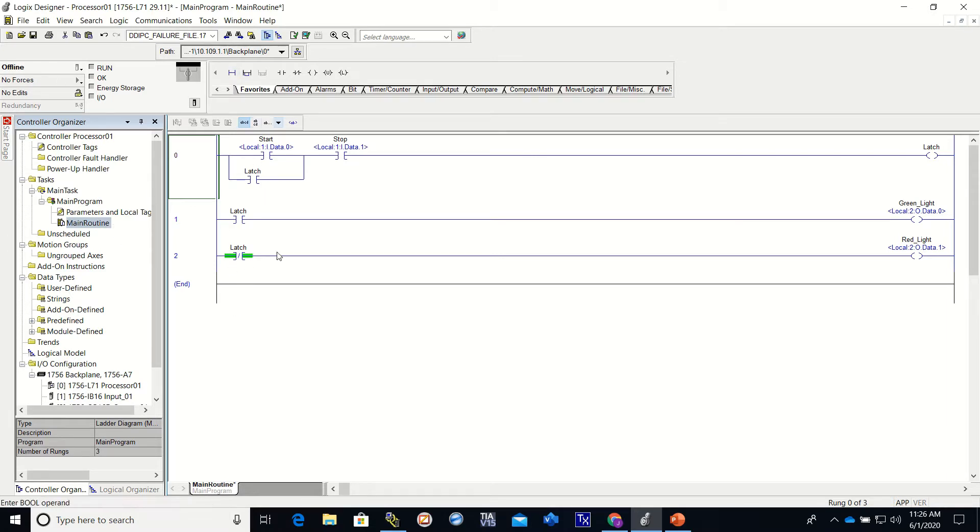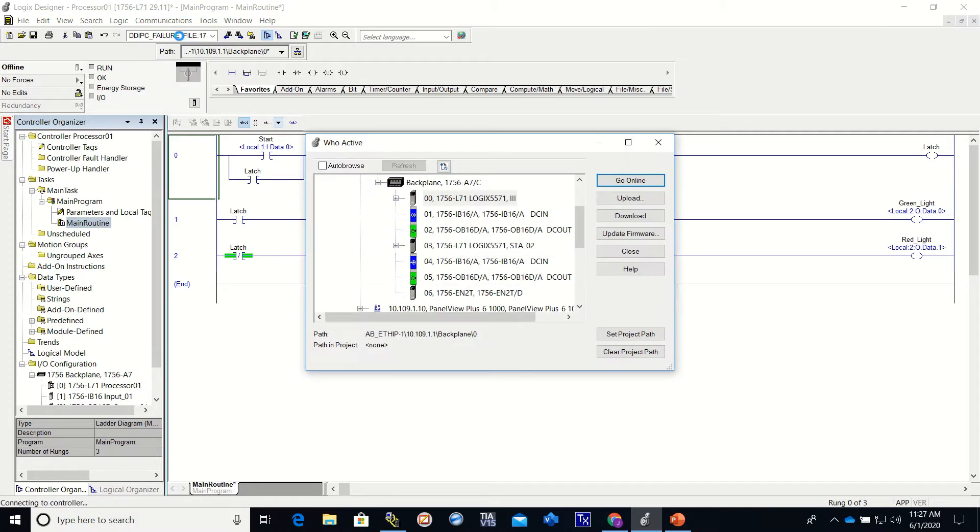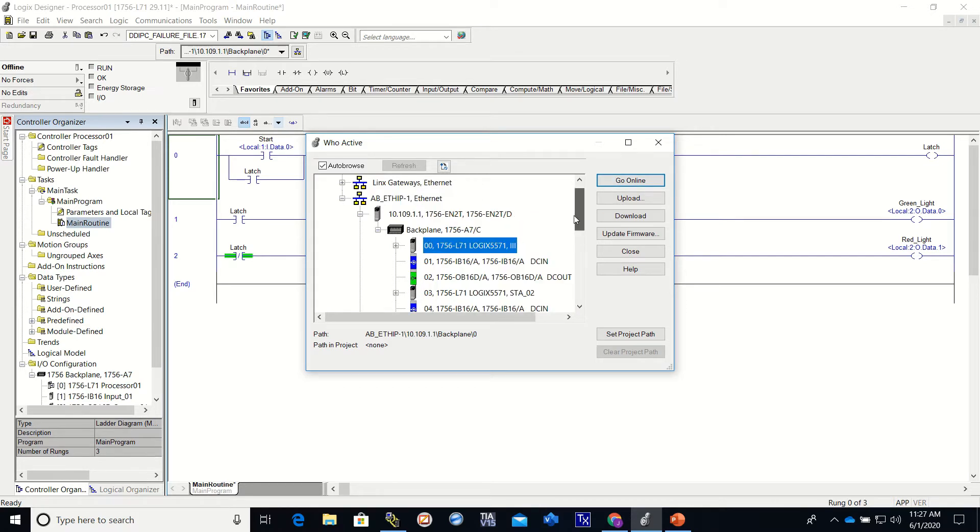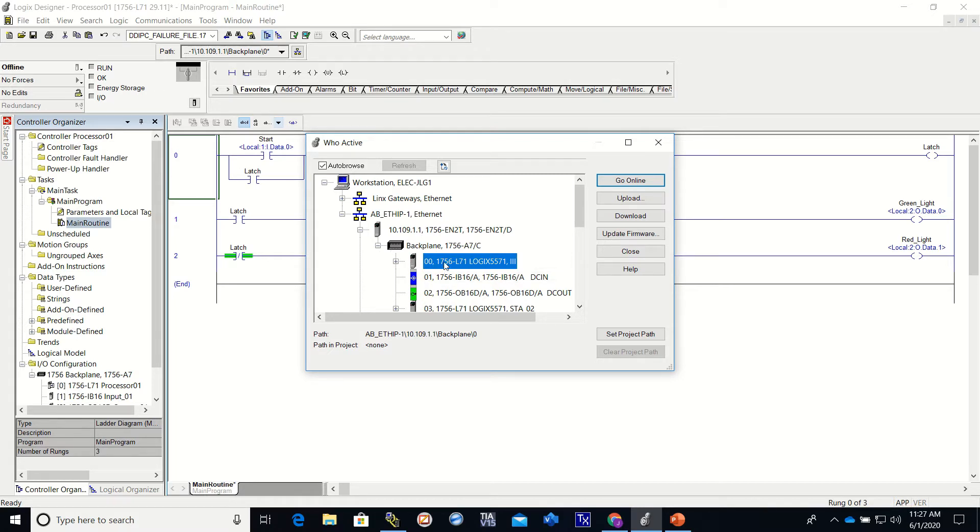The first thing we need to do: go up to Communications, Who Active. We need to select our processor, and we put our processor in slot zero. Remember our IP address was 10.109.1.1. We go through the backplane, we are connecting to the processor in slot zero, and then we just simply download.